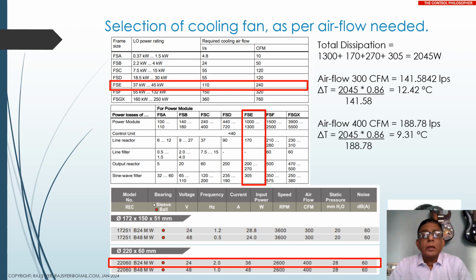Okay, so in the previous example, let us say we had a total dissipation of 2045 watts. So we say that the airflow we require is about 141.58 liters per second. Suppose you take a cooling fan with airflow at 300 cubic feet per minute, or 141.58 liters per second. Now if we were to use this fan, then the corresponding increase in temperature would be 12.42 degrees.